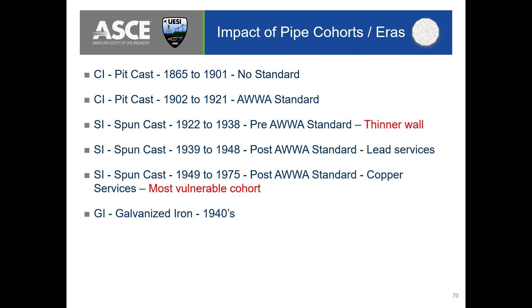And then whenever you get up into 1949 to 1975-ish, you start seeing the spun cast iron, and you'll see copper services. Because you might get some galvanic reaction there between those dissimilar metals, this is one cohort we say is very susceptible to corrosion. And then the last one we've got on this slide, talking about galvanized iron, you're again talking about a lot of corrosion. If you find something that is galvanized today, you're typically going to find something that's in an extremely corroded state.